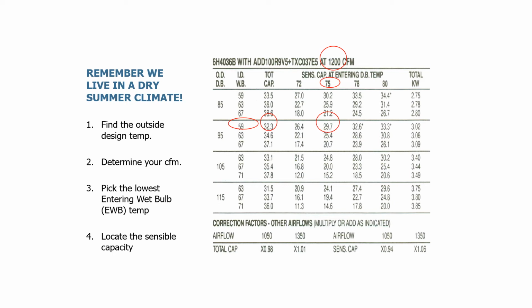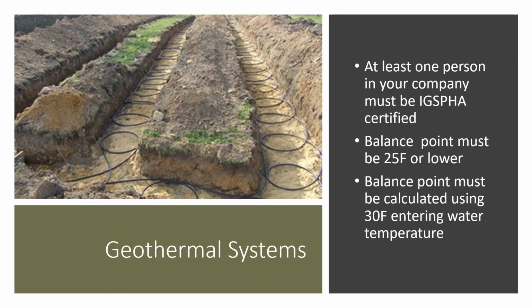Locate the sensible capacity. Well, here they give you the total, which is 32, and they give you the sensible capacity, which is 29. So this is a 3-ton machine, and they're telling you that underneath these conditions, the sensible capacity is 30,000 BTUs. It's not 36,000 BTUs. And if for whatever reason you wanted to go to a humid climate, say it's all the way up to 67, your sensible capacity would be actually less than a 2-ton machine, roughly at 21,000 BTUs.